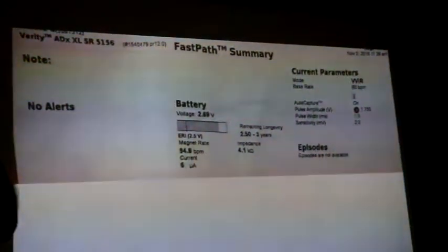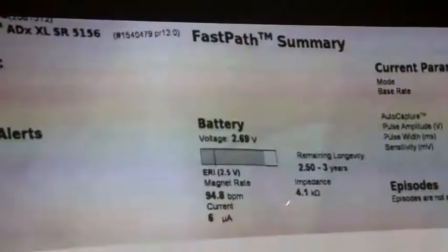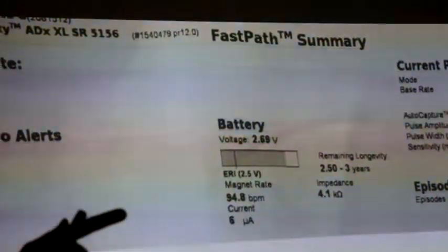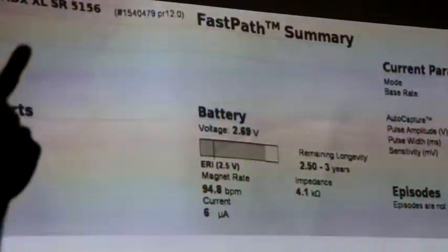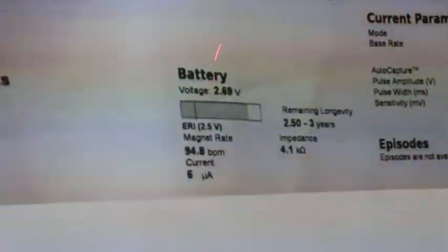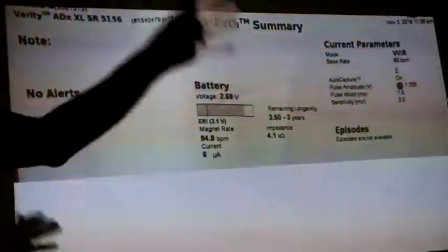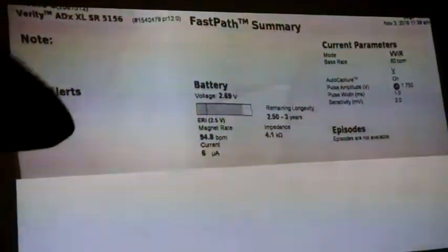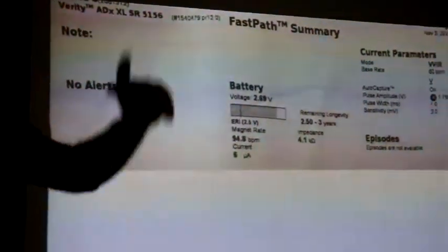What they should be looking at, and this is specific to lithium iodine chemistry, is this number. When this number gets to sort of 4 to 5 kilo-ohms, the best thing to do is to send this data here to technical services. Get their emails, send it to them. They'll send it to the person in Sweden with the enormous brain and a computer, and they will tell you exactly how long that device has. Then you don't have to worry too much about it, okay?